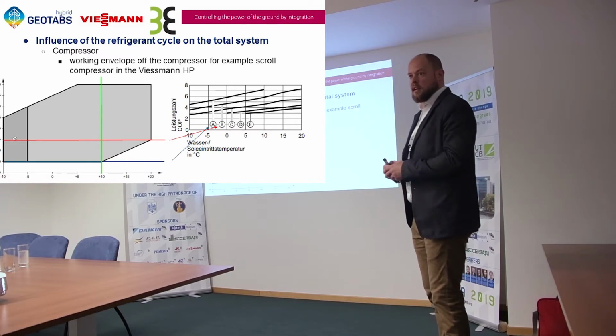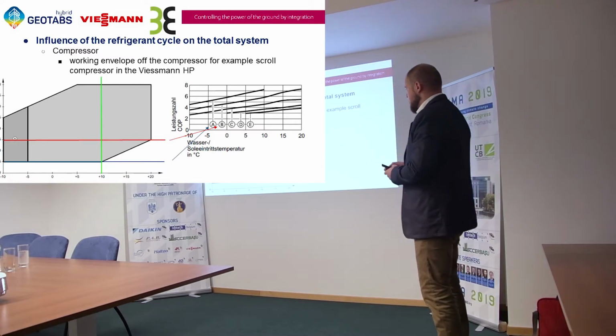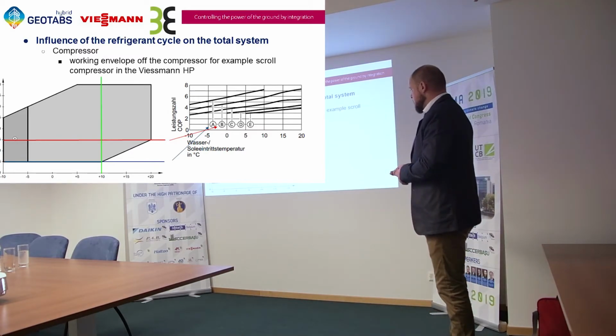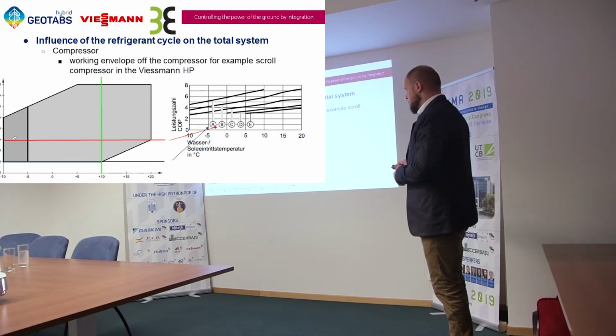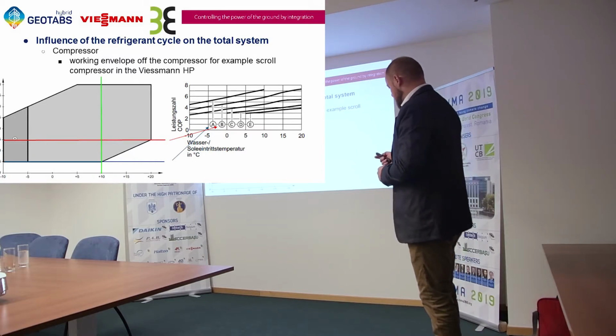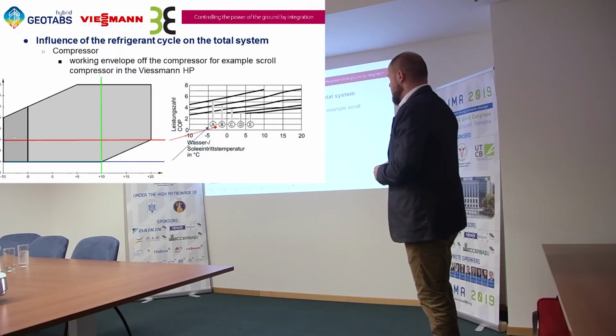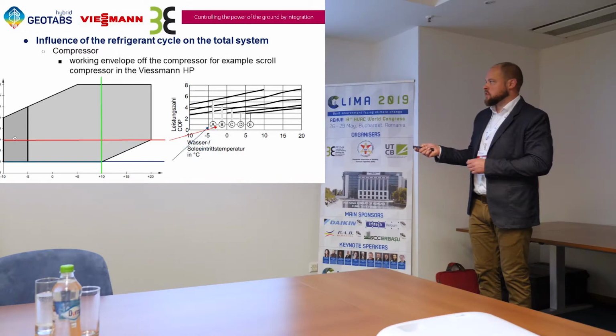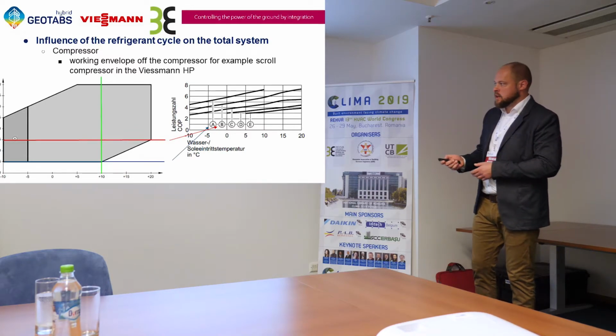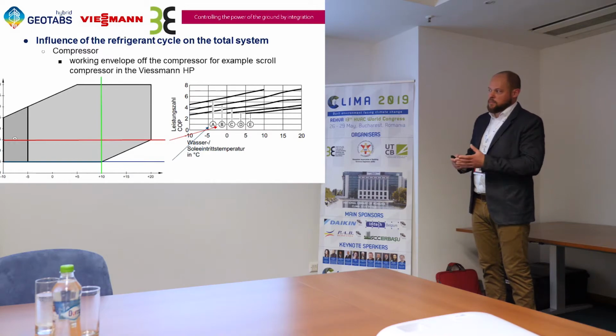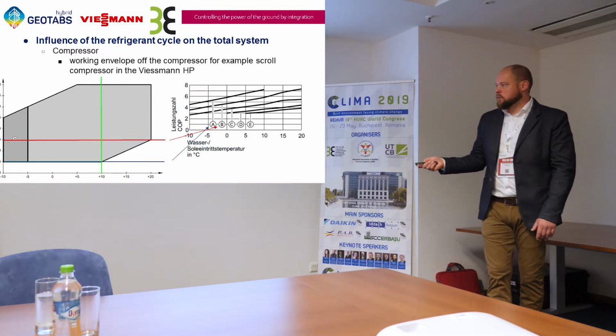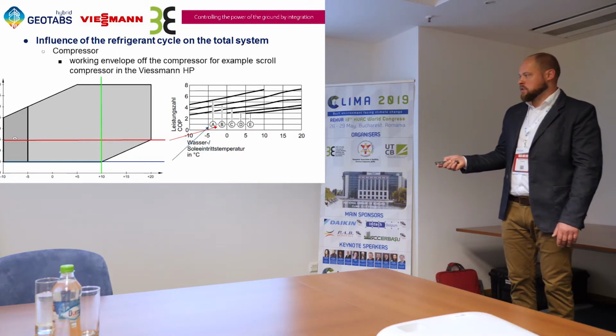That's because of the fixed pressure difference between the evaporator and the condensing side. Even with higher temperatures, like above this 10 degrees, 15, 20, we see that the departing temperature in the condenser has to be much higher because the input pressure is already high. You can also see in this envelope that with source temperatures of about 5 degrees, we can reach the maximum departing temperature of 60 degrees. This is what you can see on the top. So for the GEOTABS project, for example, I have added these two lines. With a departing temperature of 25 degrees, we can work without a problem with source temperatures of 0 to plus 10 degrees.